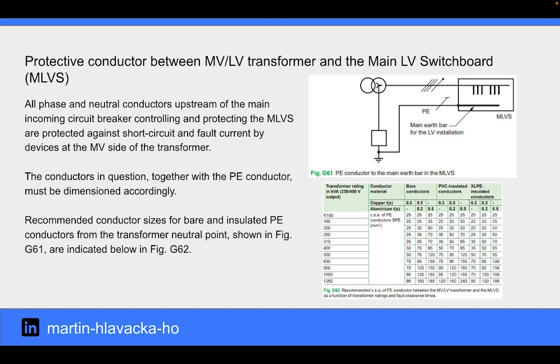Protective conductor between the MV-LV transformer and the main low voltage switchboard. All phase and neutral conductors upstream of the main incoming circuit breaker controlling and protecting the MLVS are protected against short circuit and fault currents by devices at the MV side of the transformer. The conductors in question, together with the PE conductor, must be dimensioned accordingly.